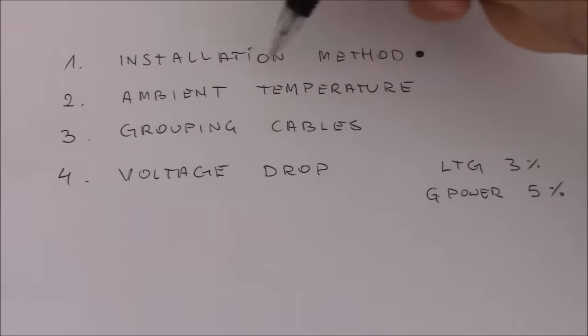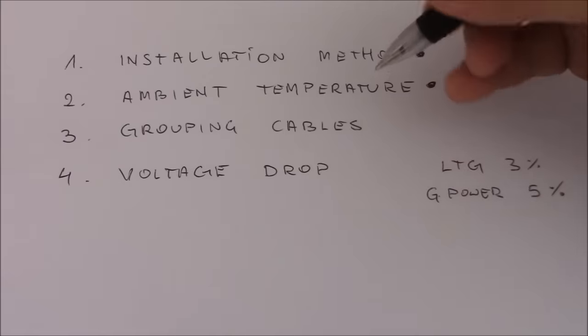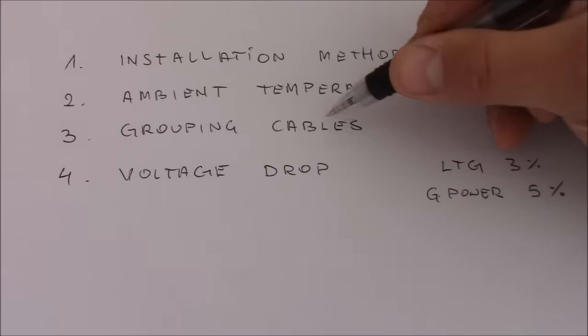Now the ambient temperature. So basically that's the surrounding temperature of the cable. Don't install the cable near boiler or near the radiator pipes as they can be easily overheated. They just cannot dissipate the heat when they're warming up.